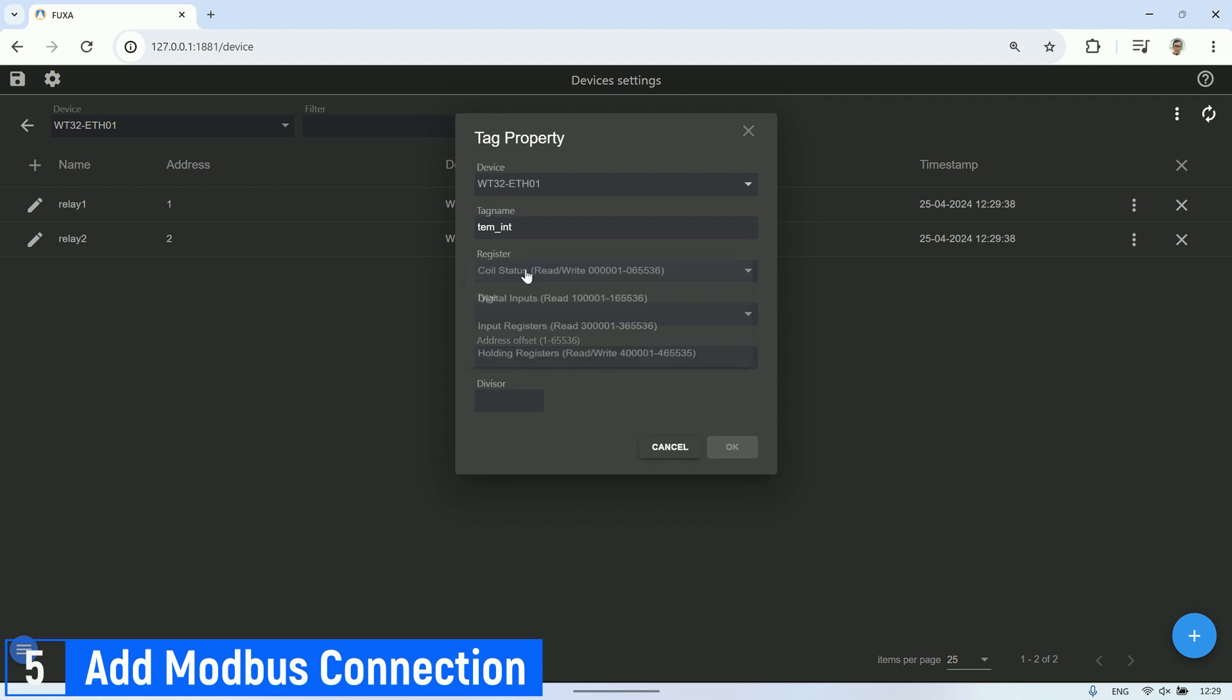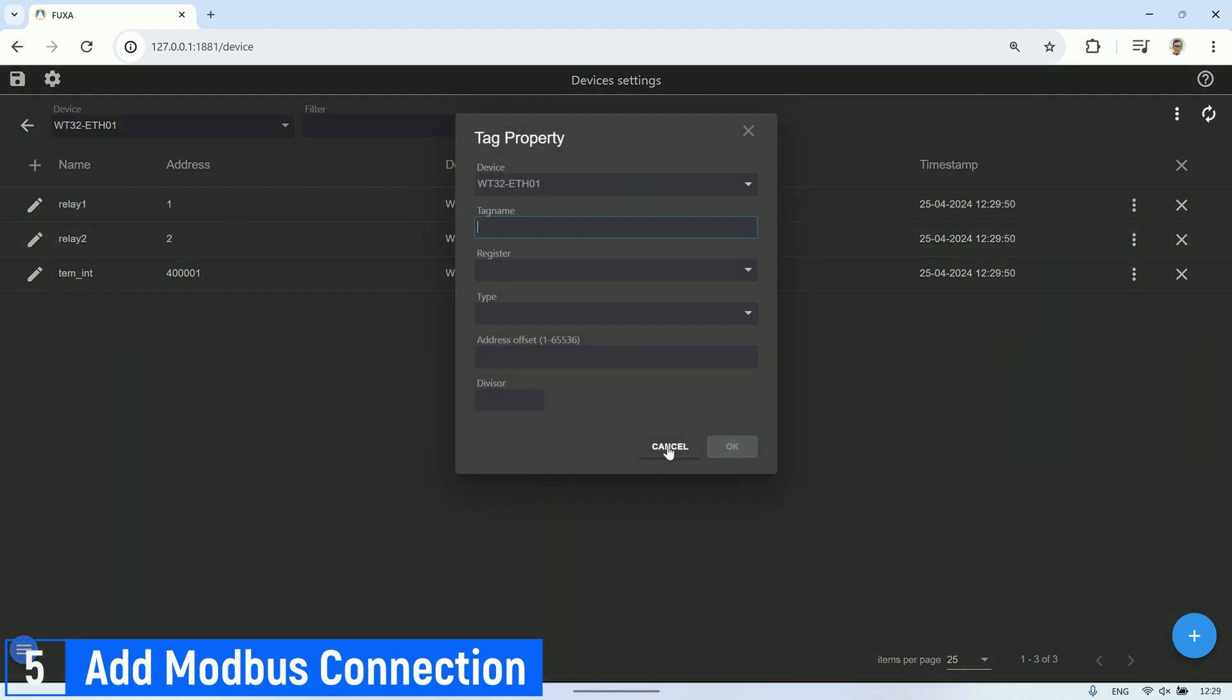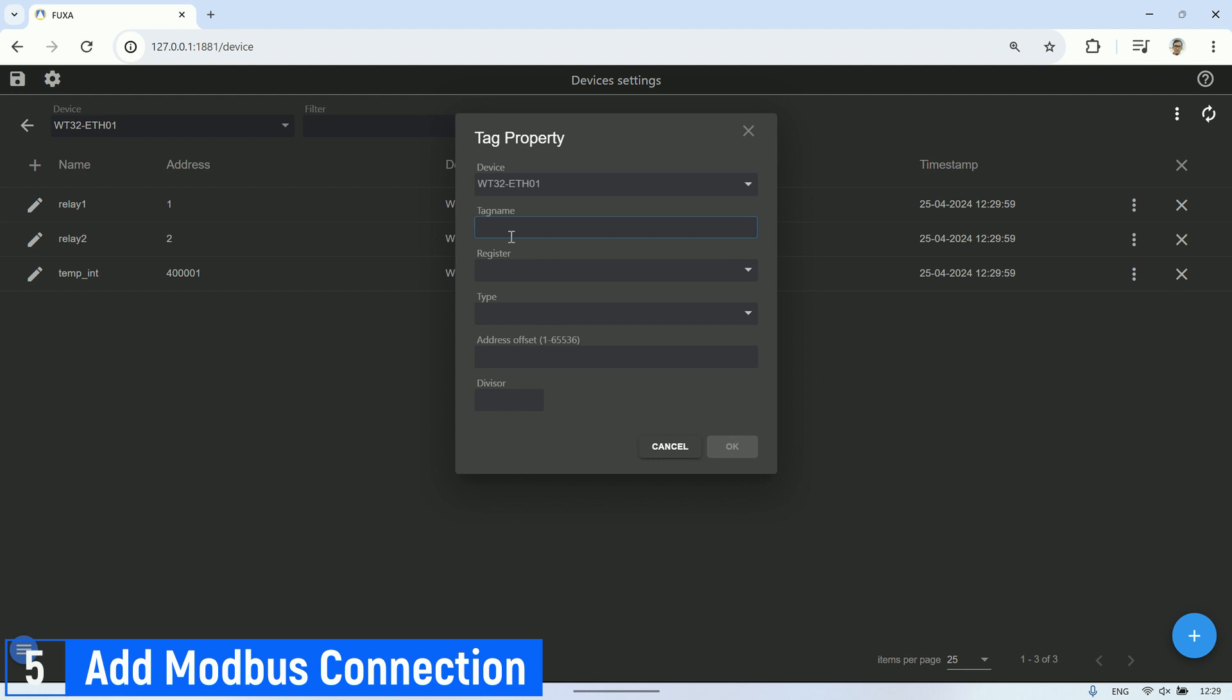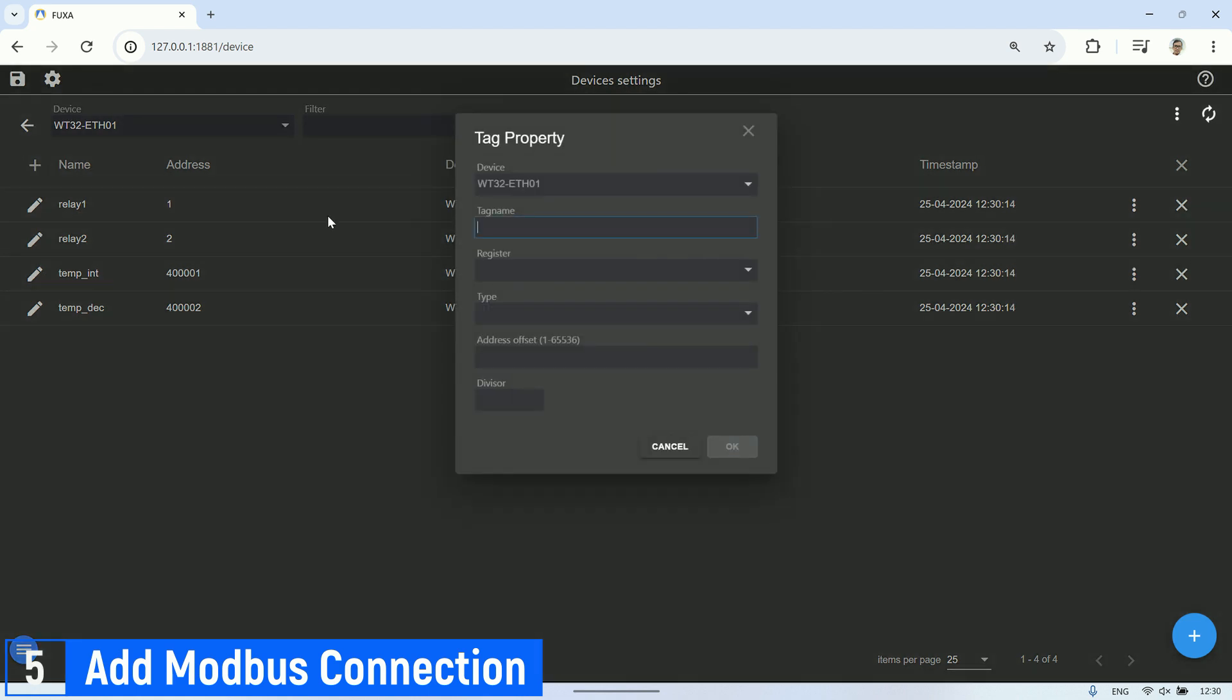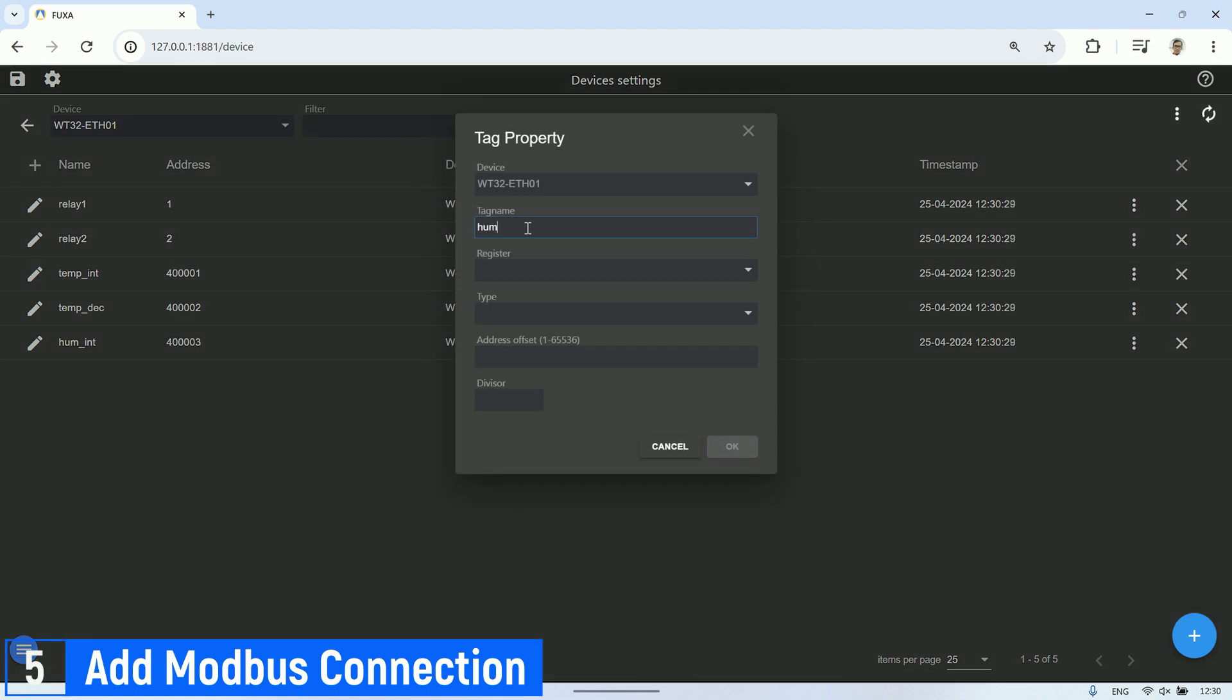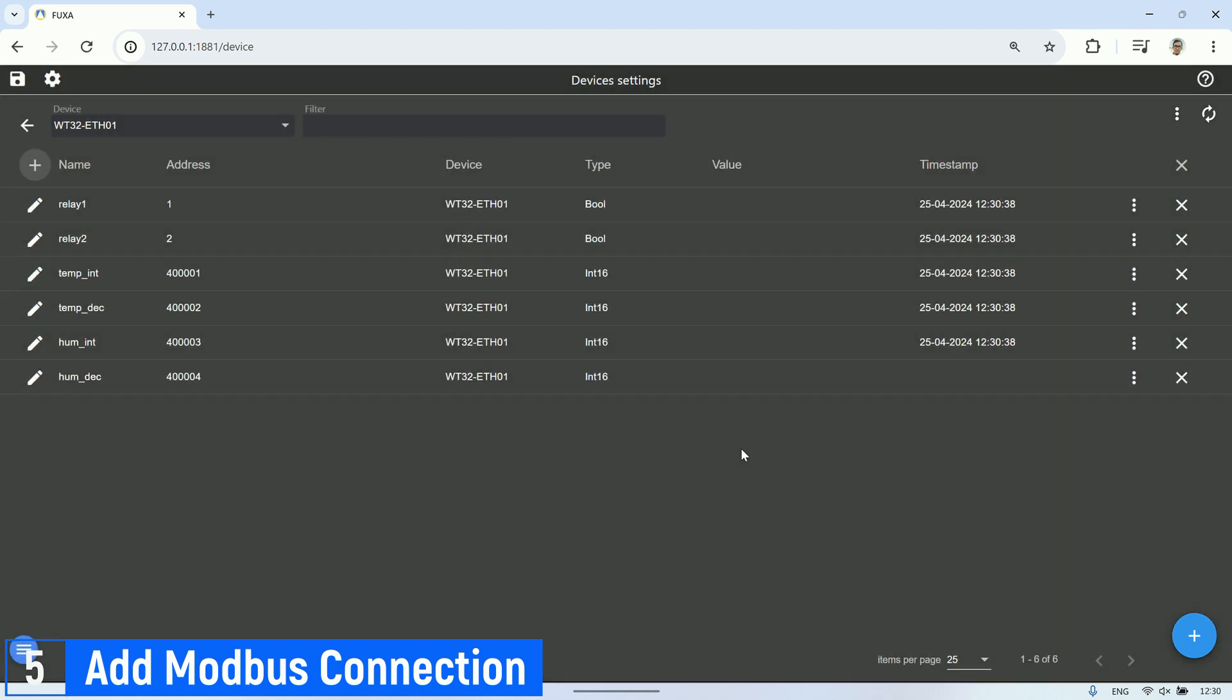Next, for the holding registers, we have four addresses in use. Two addresses are used for temperature values—one for the integer part and one for the decimal part. Since the Modbus server is only 16-bit, each address can only store an integer value. Similarly, for humidity values, we also have two addresses, one for the integer part and one for the decimal part. In the device settings for the Modbus TCP server, we've created tags for the addresses from which we'll retrieve values. We can now view the real-time values for each address in this table.